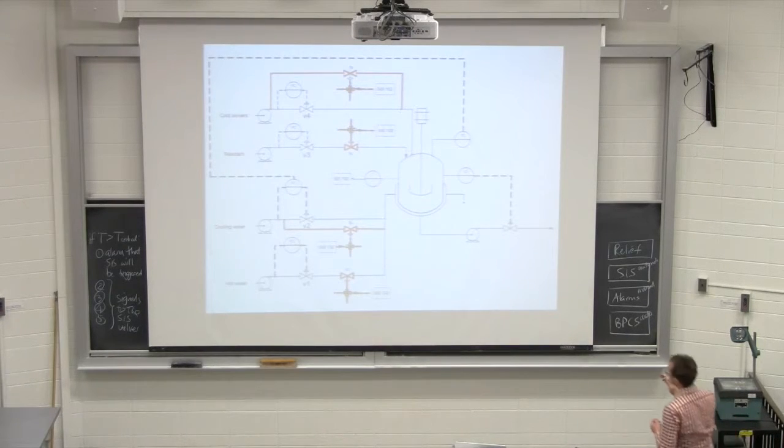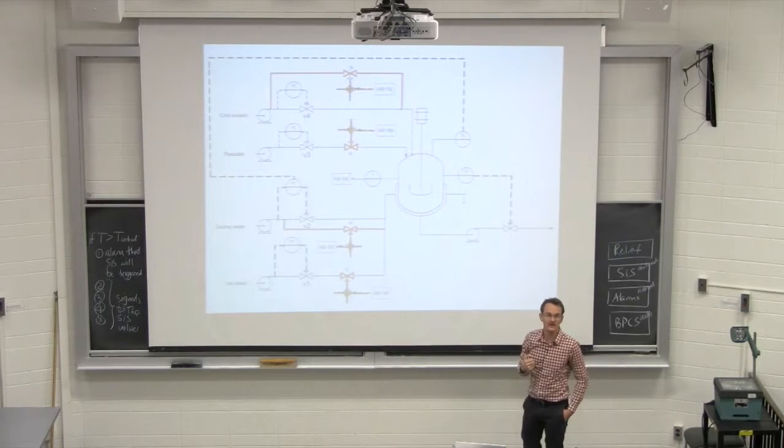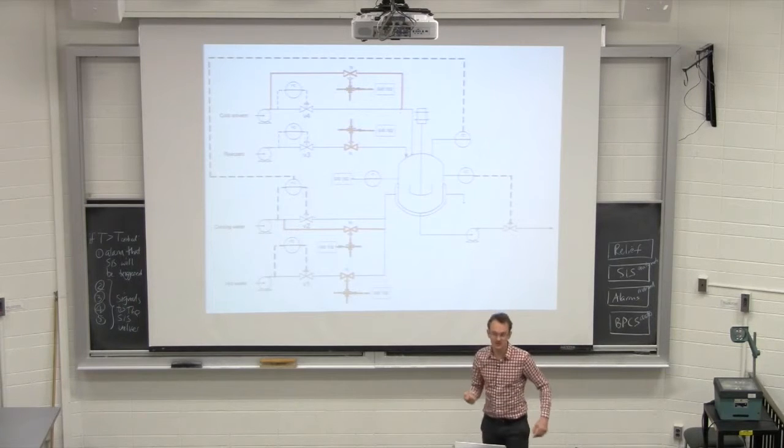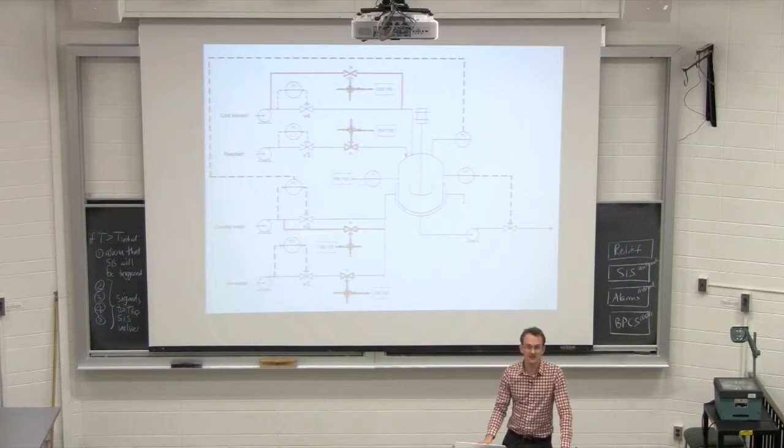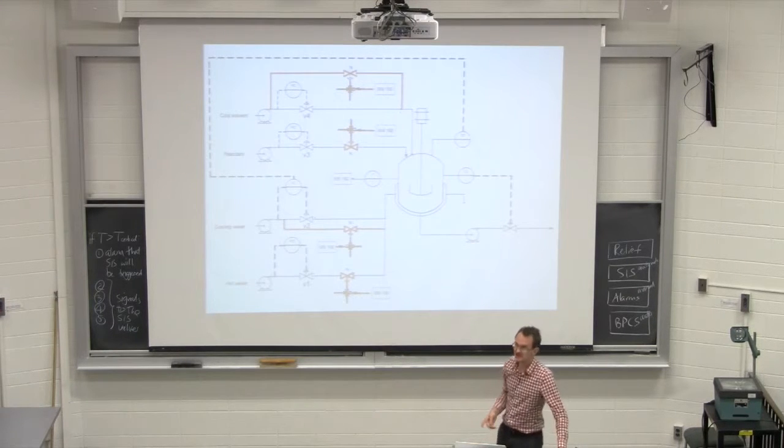So as drawn here, this CSTR, if it's pressurized, does not have the relief system required. In your project, you'll also be going back to your P&ID and investigating units that need relief. So any time we have a closed system, we must provide relief.